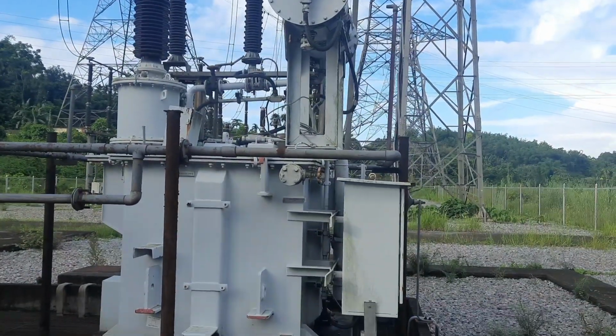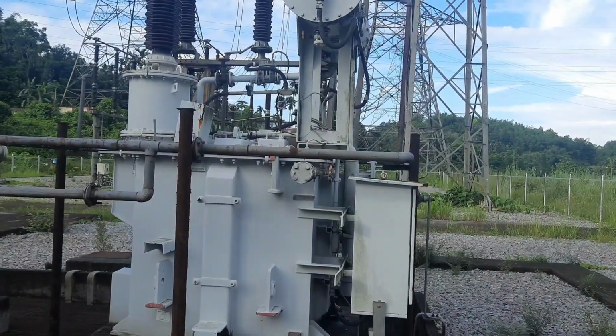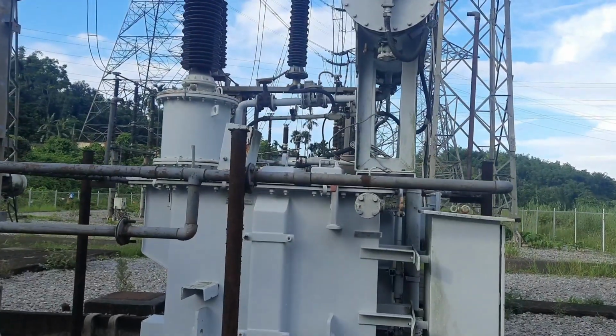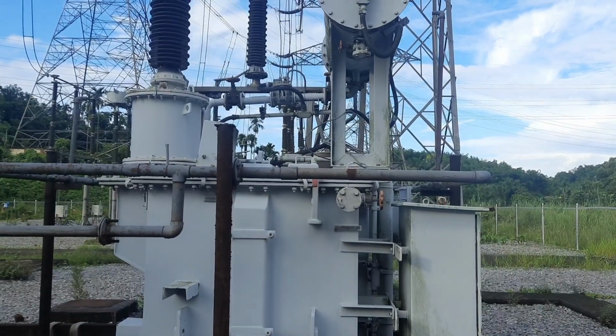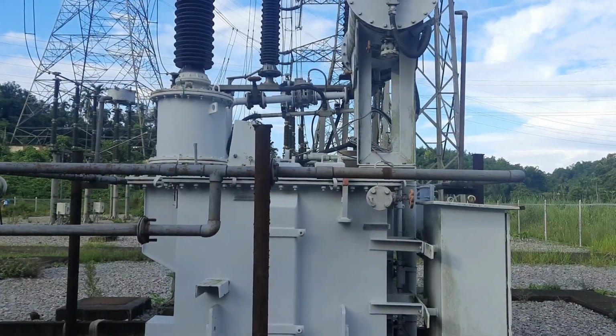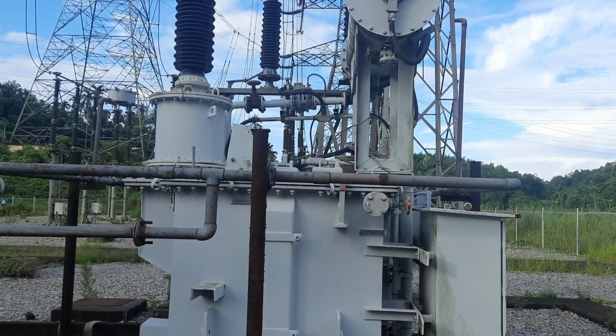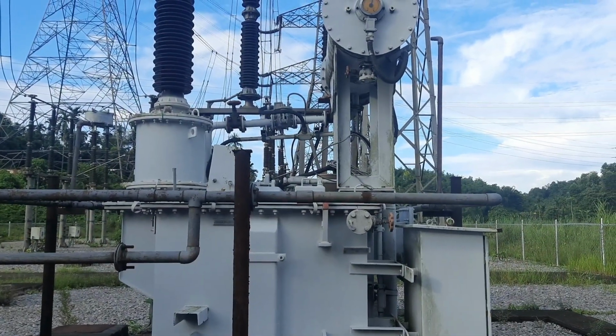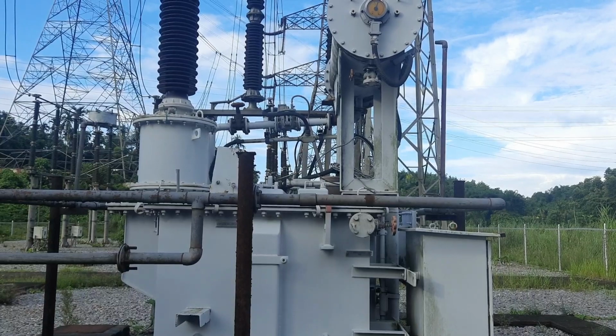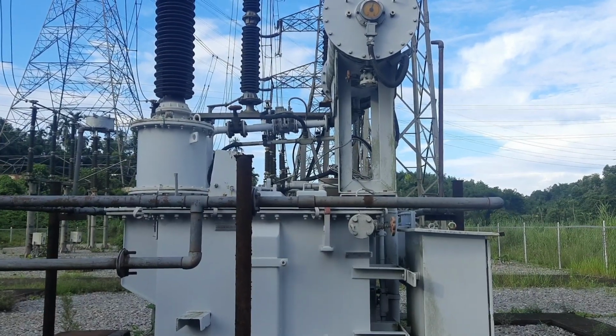always in all, whether it's a reactor or a transformer. Only one basic thing is that it is installed in between the conservator and the main tank, and that's all. No matter where you install it, it should be between the main tank and the conservator tank. And also one thing, it should incline at an angle of 2 to 5 degrees towards the conservator tank.